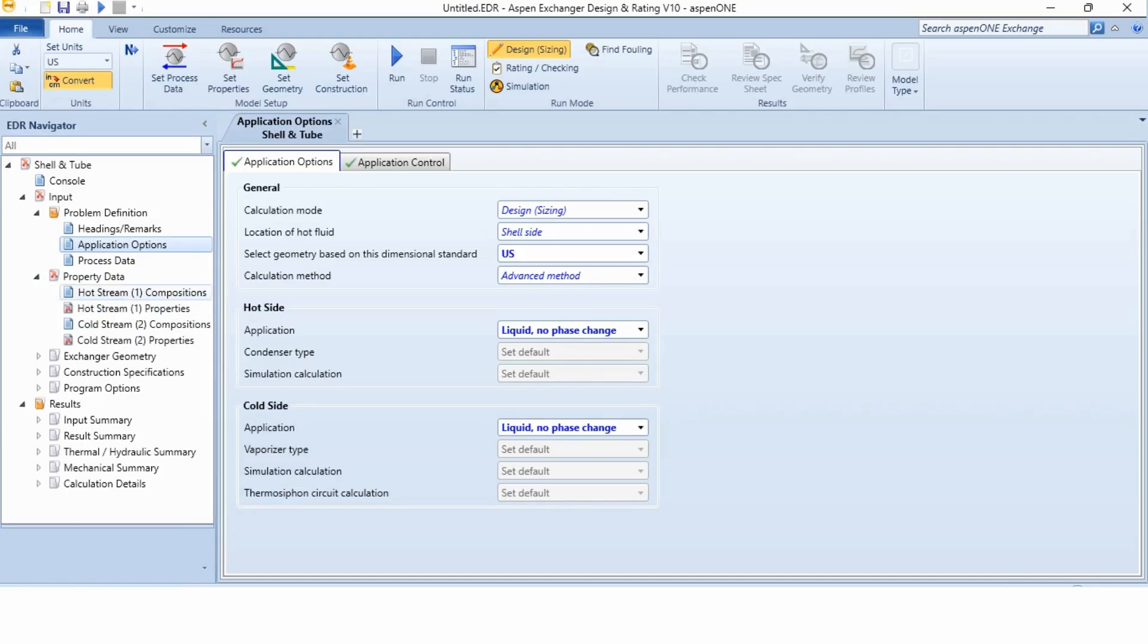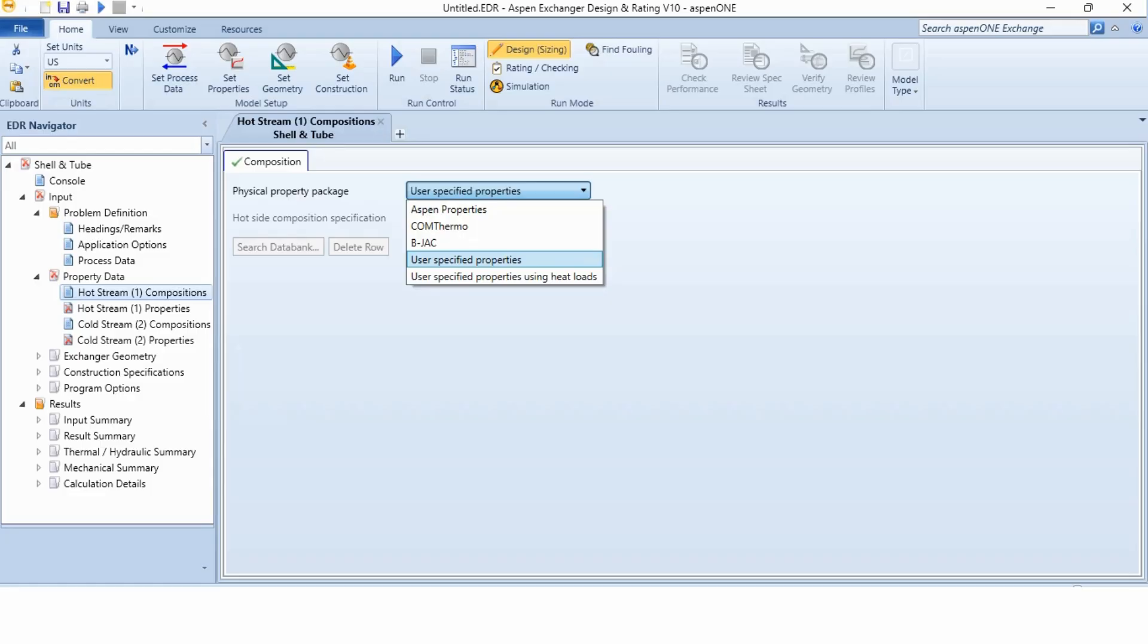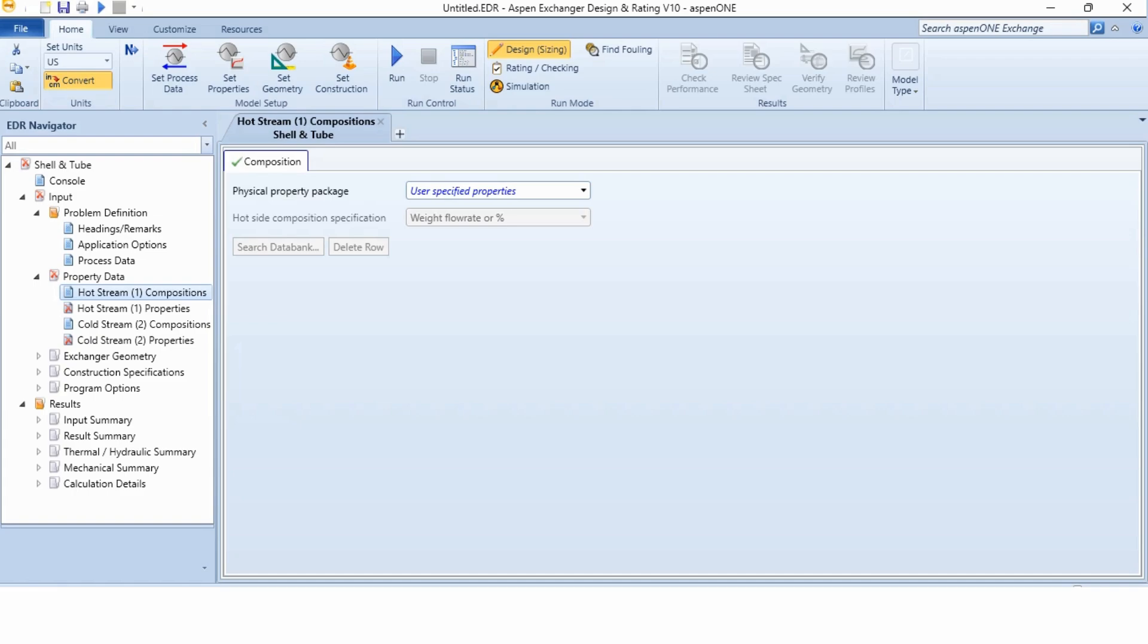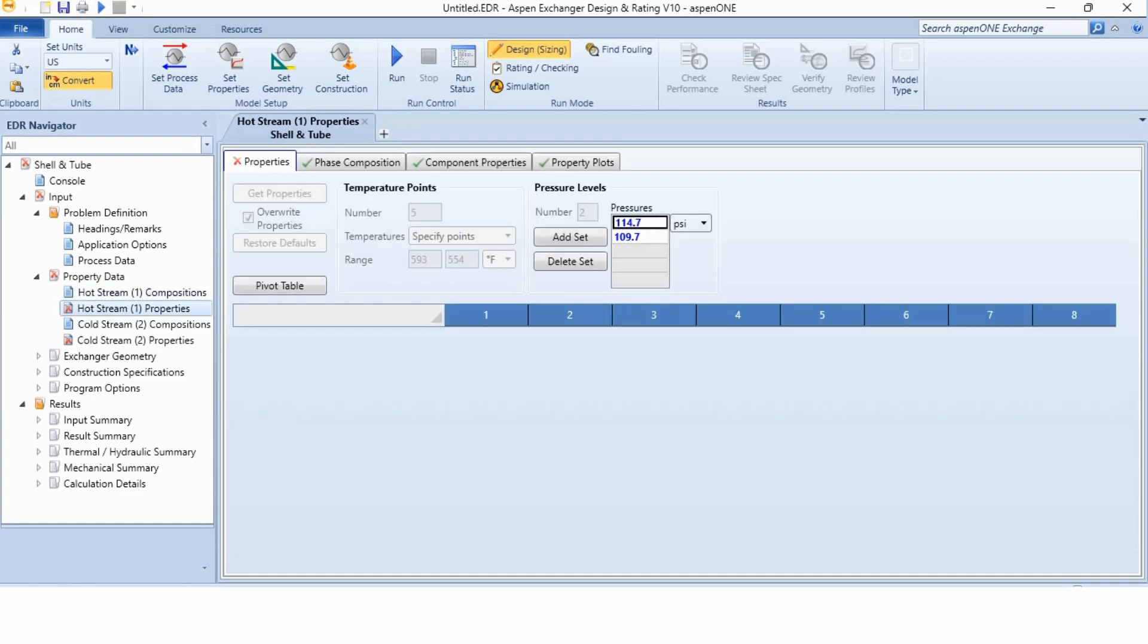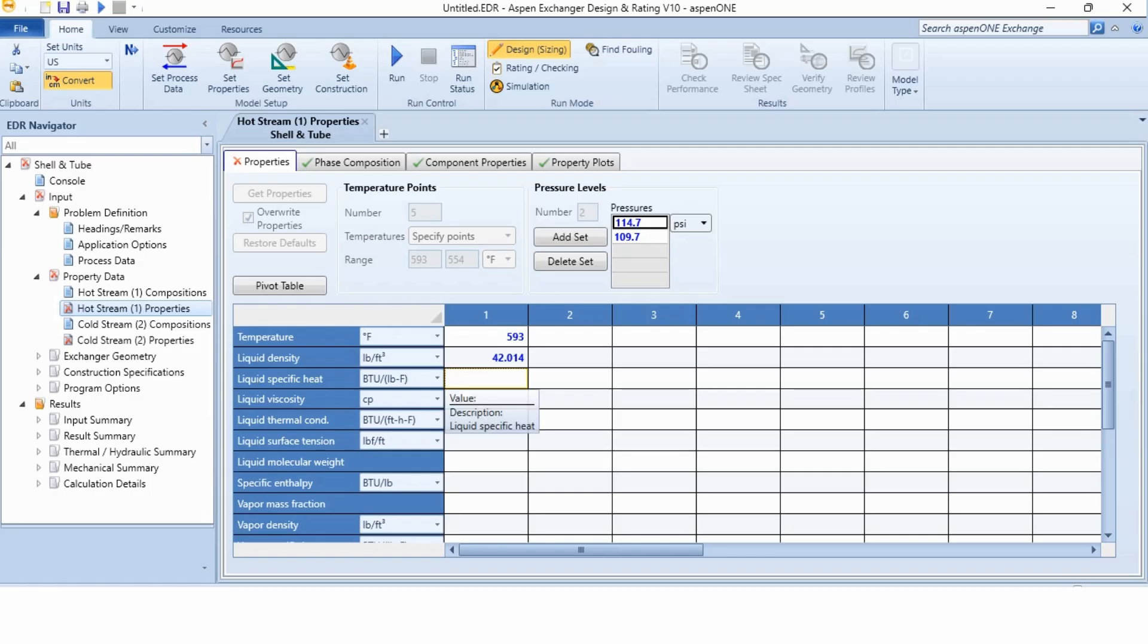Now going to the property data, earlier we used to specify the composition by selecting some other option like Aspen properties, COMThermo, B-JAC. But now we will select the user specified property and where we can specify it in the second part, which is hot stream properties. And now we can specify the required data over here. Like what is that data for the hot stream 593 degree Fahrenheit, 42.014 pound per cubic foot of density, 0.698 specific heat capacity, viscosity is 0.284 and thermal conductivity is 0.05.